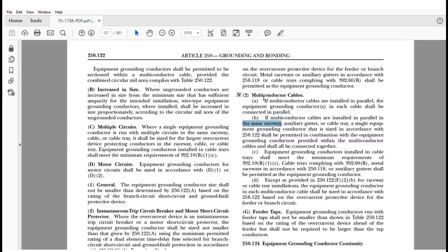Okay, so now we're just talking about multi-conductor cables installed in a raceway, auxiliary gutter, or a cable tray. It is telling us that a single equipment grounding conductor that is sized in accordance with 250.122, again, shall be permitted in combination with the equipment grounding conductors provided within the multi-conductor cables and shall all be connected together.